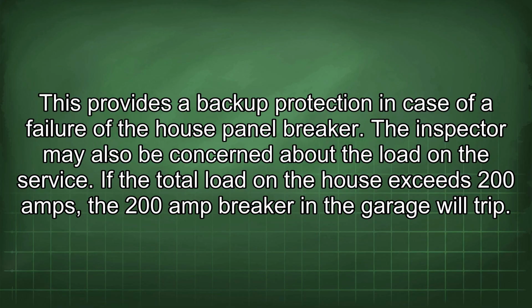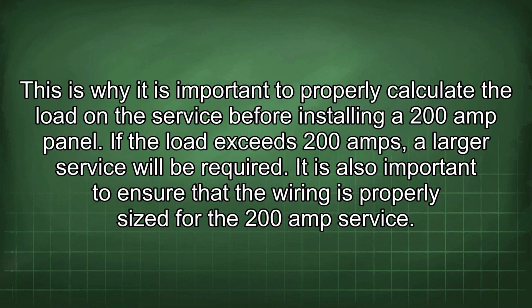The inspector may also be concerned about the load in the service. If the total load in the house exceeds 200 amps, the 200-amp breaker in the garage will trip. This is why it is important to properly calculate the load on the service before installing a 200-amp panel. If the load exceeds 200 amps, a larger service will be required.